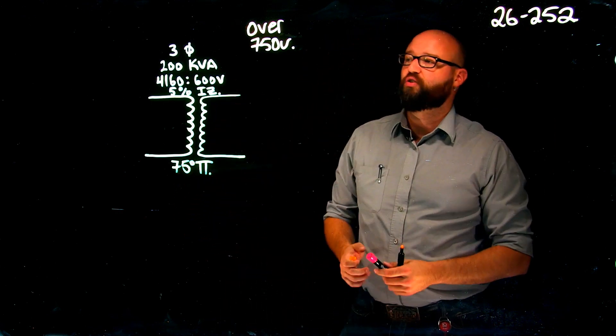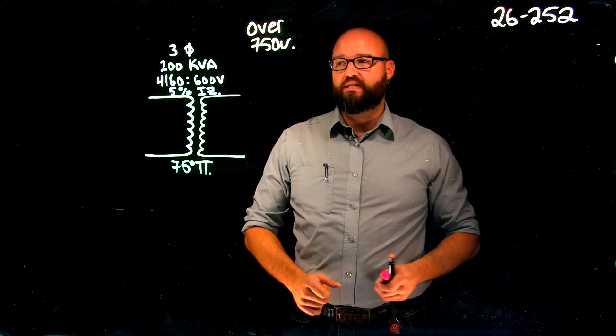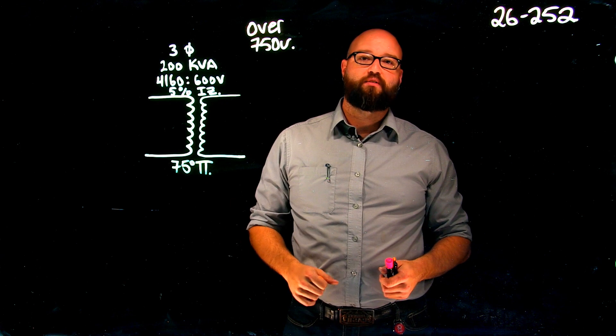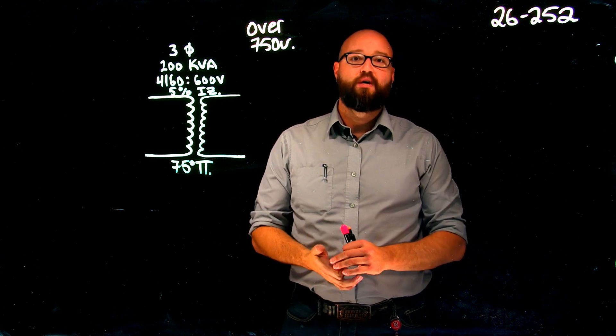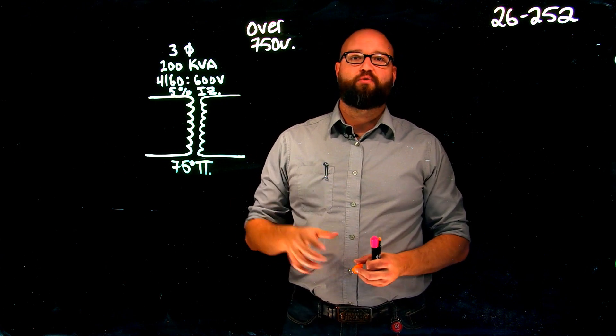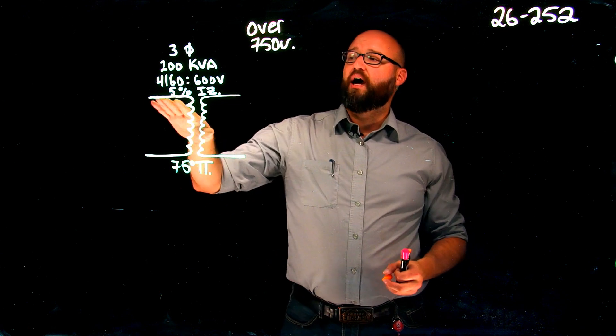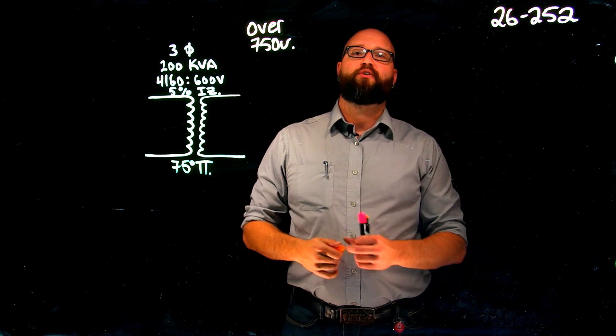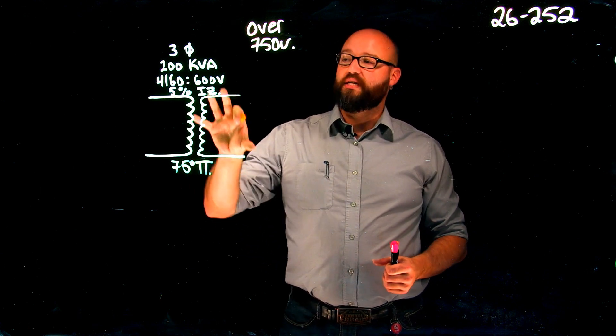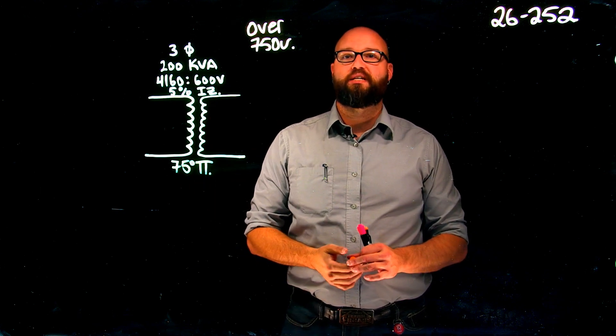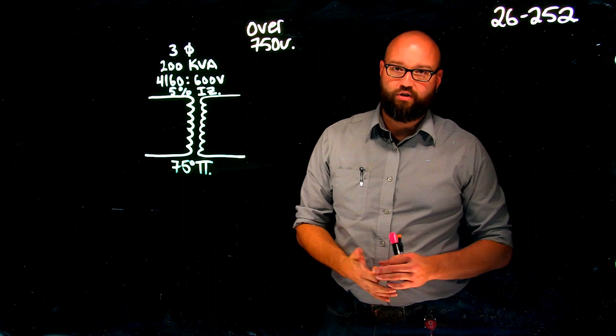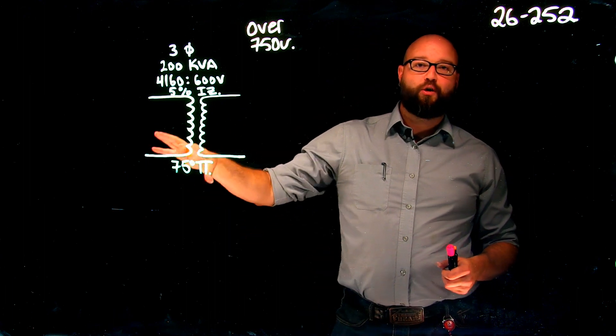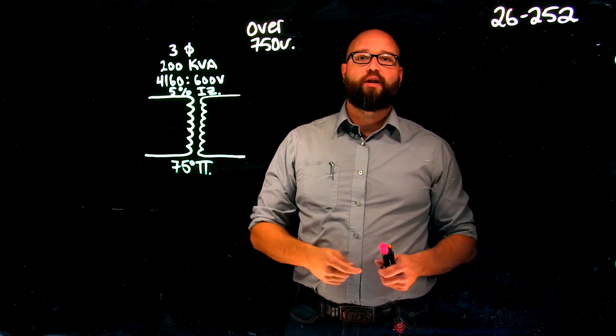We have a 200 kVA transformer, 4160 step down to 600 volts. Take note, it is a three phase transformer. Previous videos, we talked about what we do with three phase calculation. We have a 5% IZ on this transformer. When we're dealing with high voltage transformers, we need to be cognizant of that percent IZ because it's going to help us determine our overcurrents. As always, we need to figure out what is our primary rated current and secondary rated current.